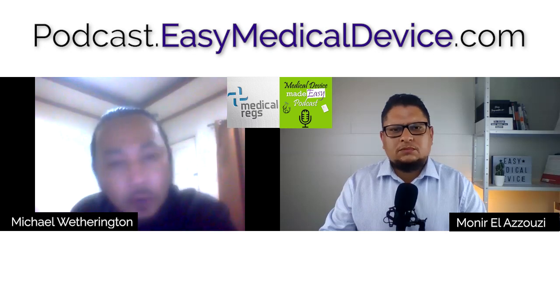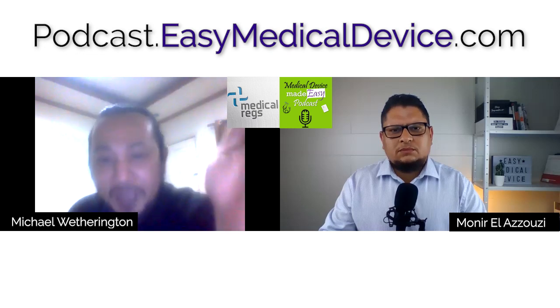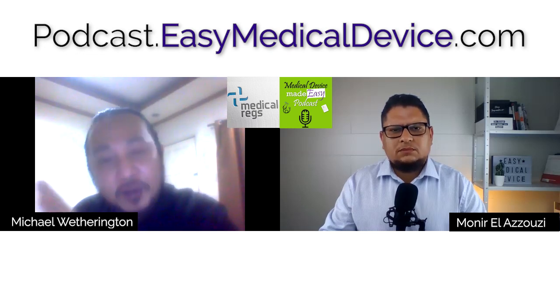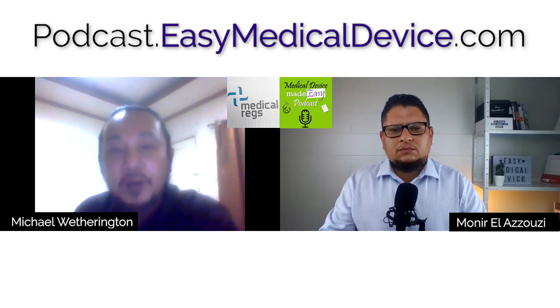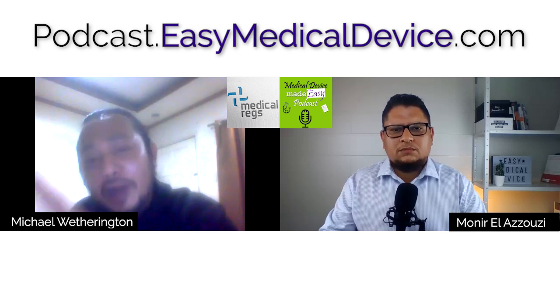So you have to seek those specific ones, and then you have to narrow that. Not all accreditations are the same. Some labs are accredited for specific standards or product categories. So just because it says accredited testing lab, or an NRTL, which is the acronym for nationally recognized testing laboratory in the US, it doesn't necessarily mean they're actually accredited for the specific standard that you need. So you have to look deeper into that. You can either ask them directly, are you accredited as an NRTL for 60601, the US version of that? They can either say yes or no. If not, you can do your own research through the OSHA NRTL website, where you can actually see each of the accredited testing labs within the United States and what they have been accredited for in terms of product categories and standards. So there are qualifications other than accreditations that you have to look at.